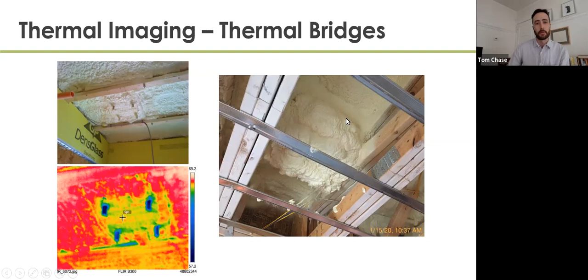On the upper left is actually an anchor for a fall arrest tie down, on the roof so that when folks are working on the solar panels up there, they can be safely secured. This means we don't need to build a barricade at the roof edge or a high parapet. But what we do have are long steel bolts coming through the roof assembly. We demonstrated there's a little bit of a thermal bridge there, and added some additional spray foam at the underside of the roof to address it.